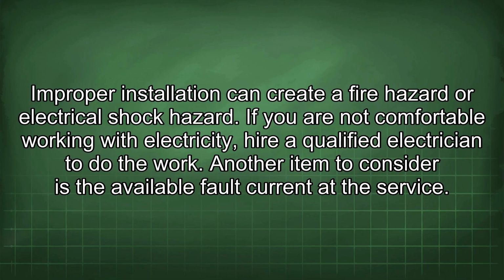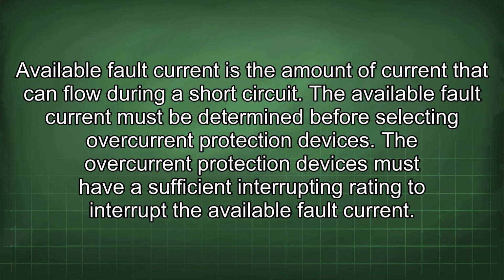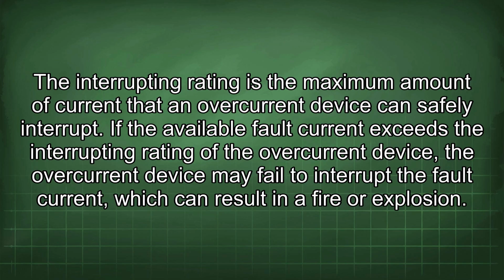Another item to consider is the available fault current at the service. Available fault current is the amount of current that can flow during a short circuit. The available fault current must be determined before selecting overcurrent protection devices. The overcurrent protection devices must have a sufficient interrupting rating to interrupt the available fault current. The interrupting rating is the maximum amount of current that an overcurrent device can safely interrupt. If the available fault current exceeds the interrupting rating, the overcurrent device may fail to interrupt the fault current, which can result in a fire or explosion.